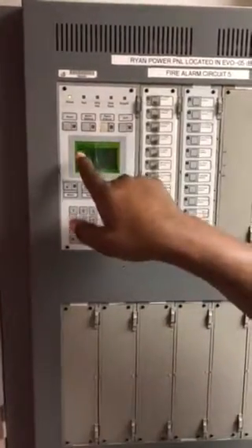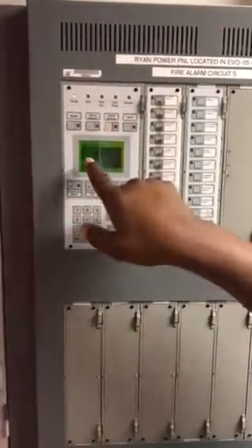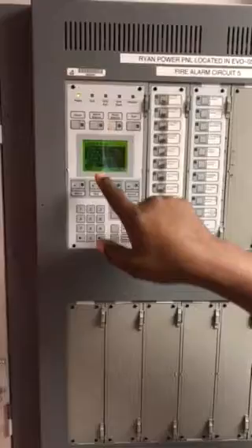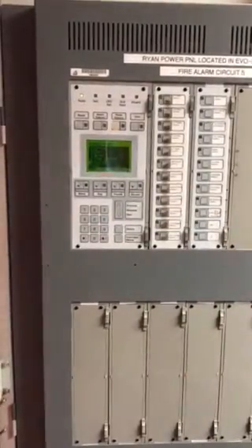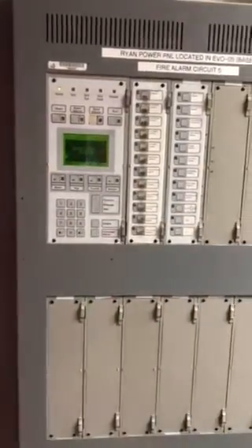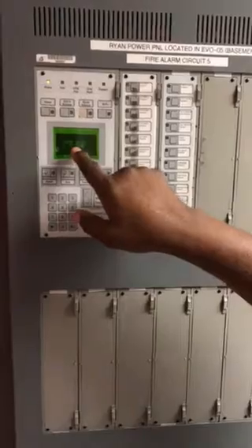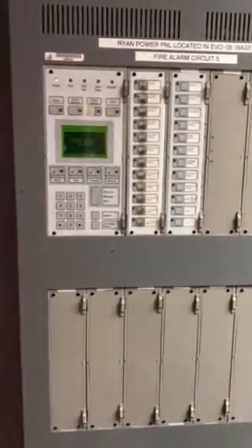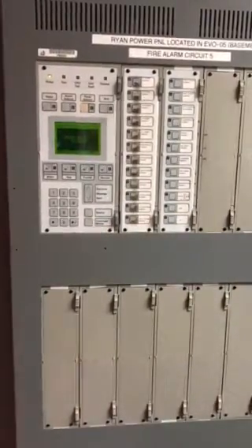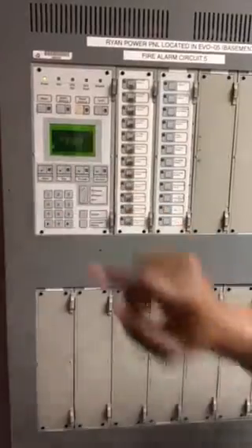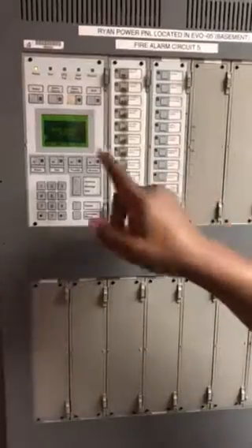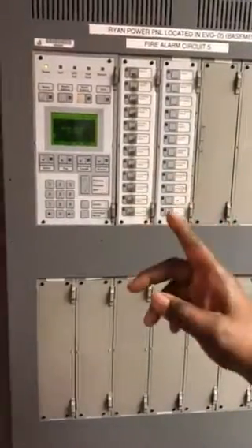Now, you see number 1 pops up. It says device, 2 is card, 3 is group, 4 is time control, 5 switch, 6 LED. We're going to look at the device, so we push the enter key again. And it's asking us to enter a device number. Now you notice that there are 8 digits here. 1, 2, 3, 4, 5, 6, 7, 8. The first 2 digits signify the panel. This is panel number 1. That's where we are. The second 2 are the loop that it's a part of. And the last 4 are going to be the location and address of the device.